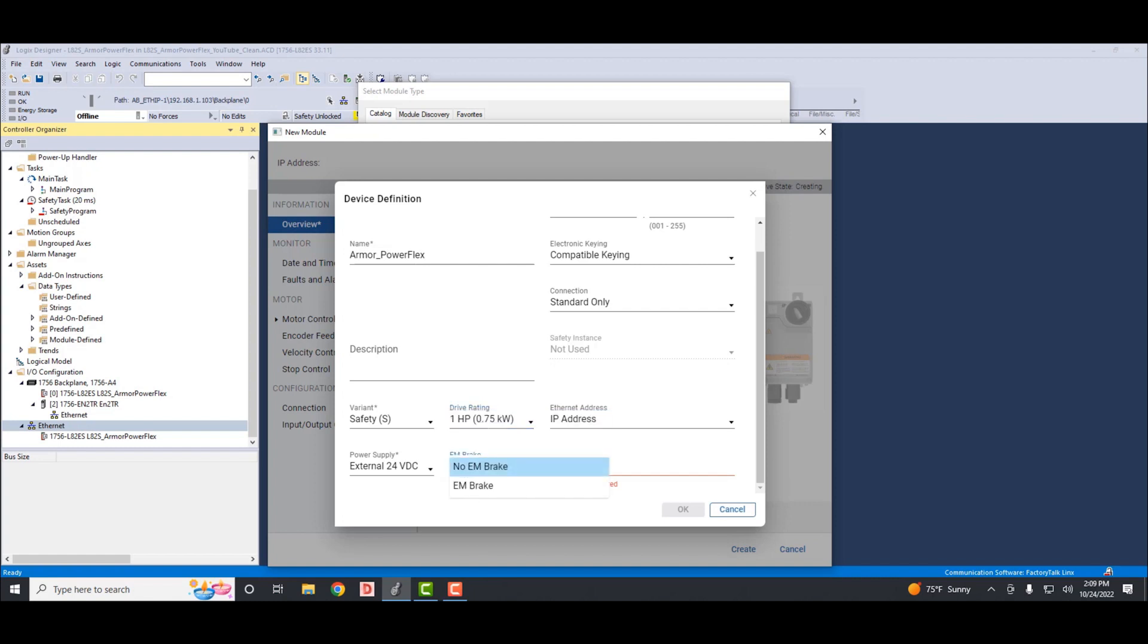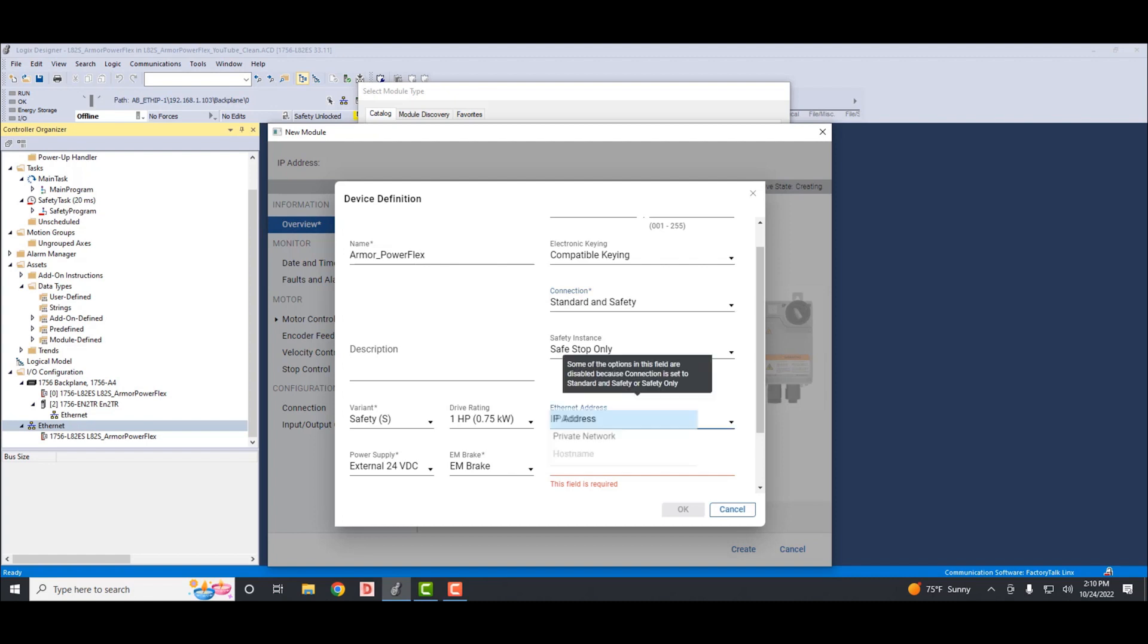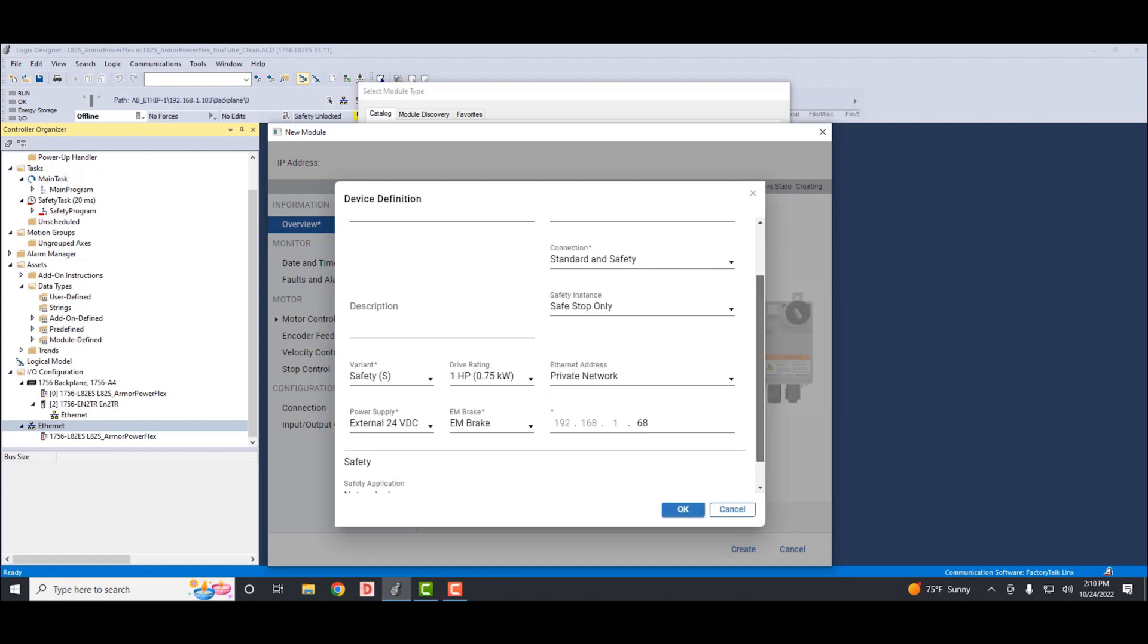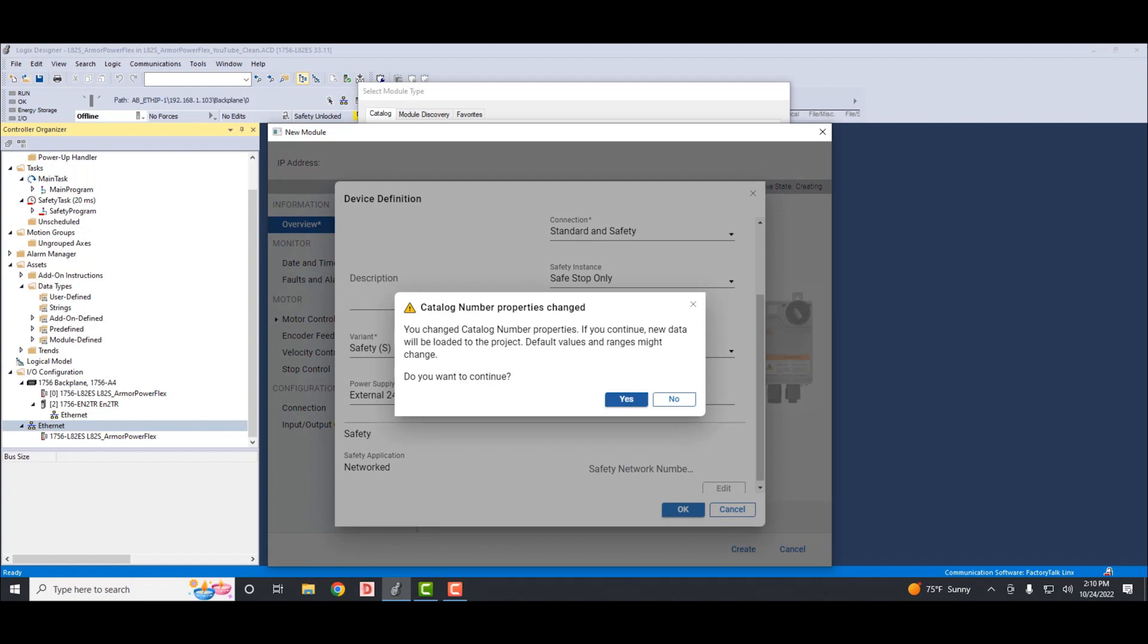Then we'll select the brake. This is with or without EM brake. Our drive is with the EM brake. And we'll go to the connection. This has three options: standard, standard and safety, and safe only. We'll want to select the standard and safety. Then the Ethernet address will be a private network, and ours will be set to 192.168.1.68. Now we will accept the edits by clicking OK at the bottom of the tab.